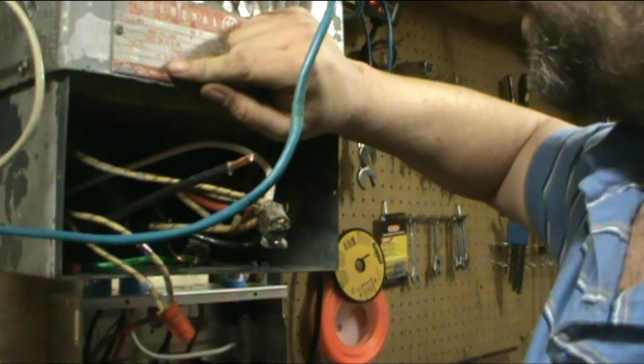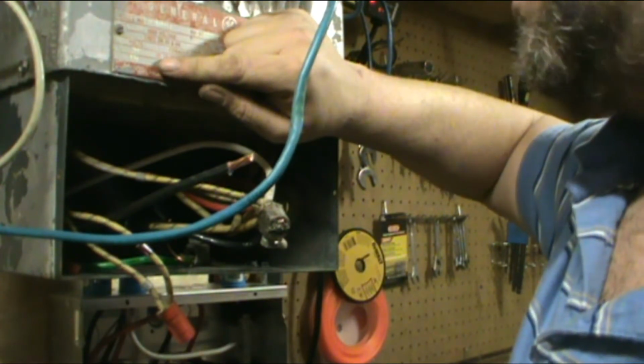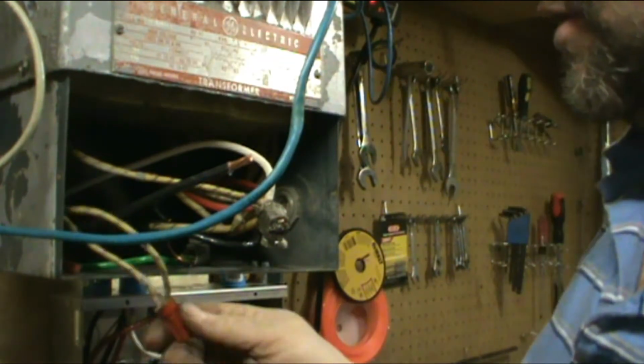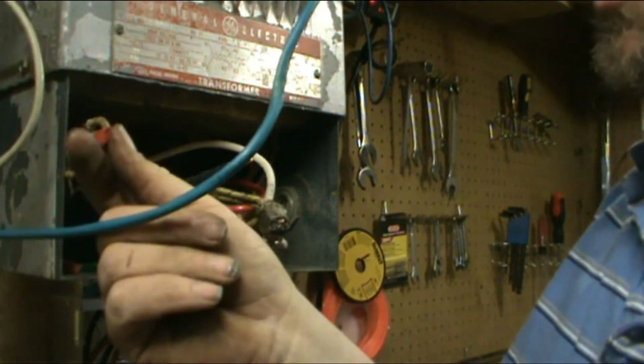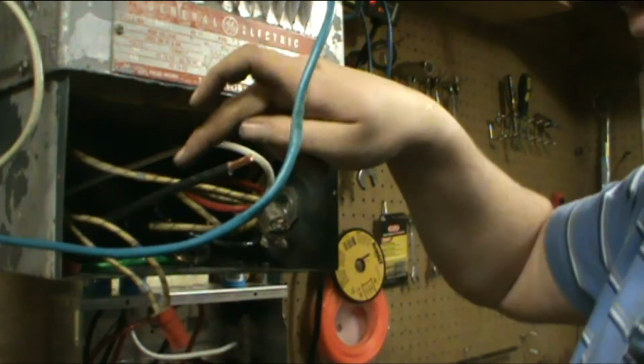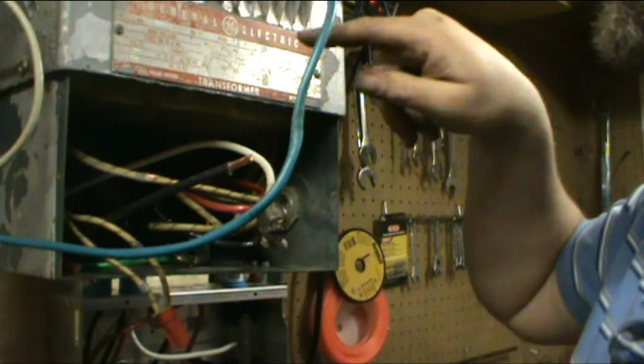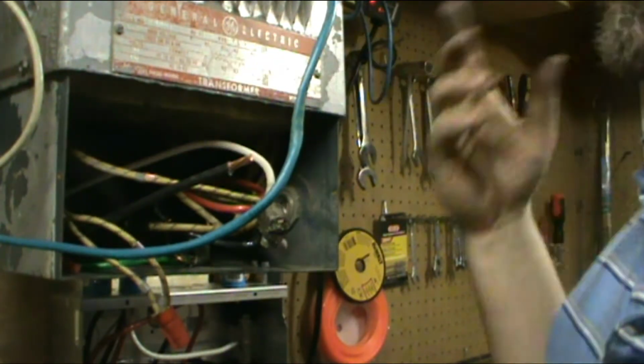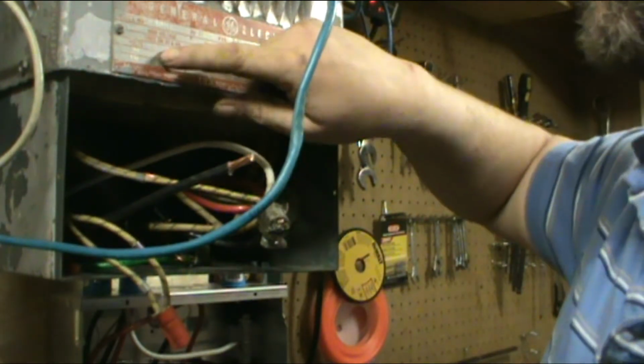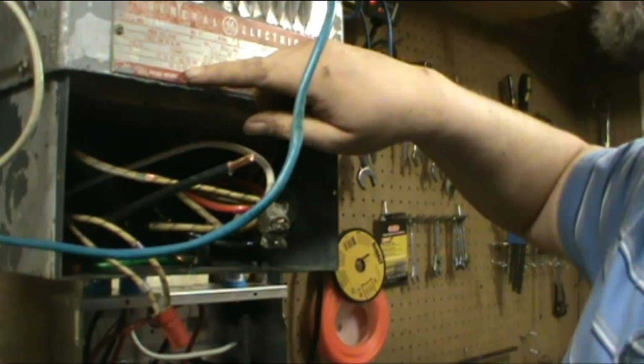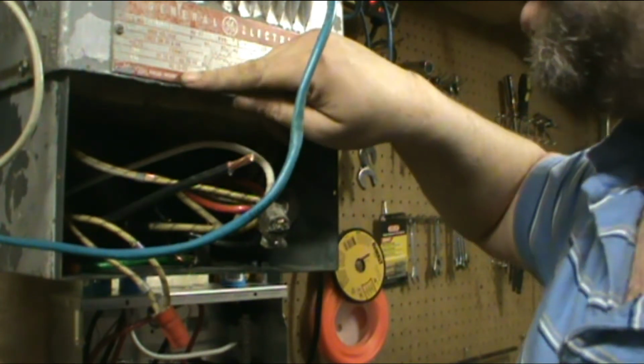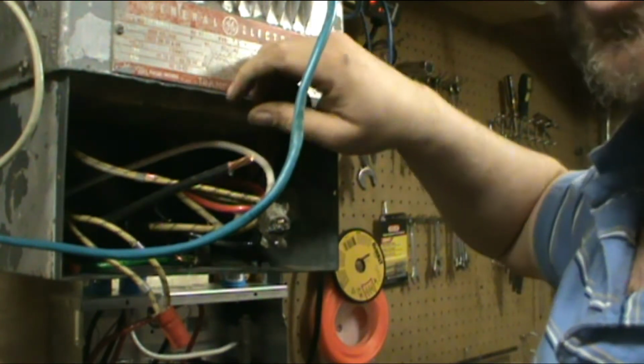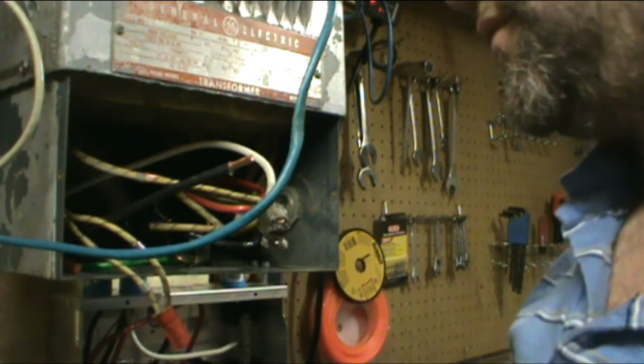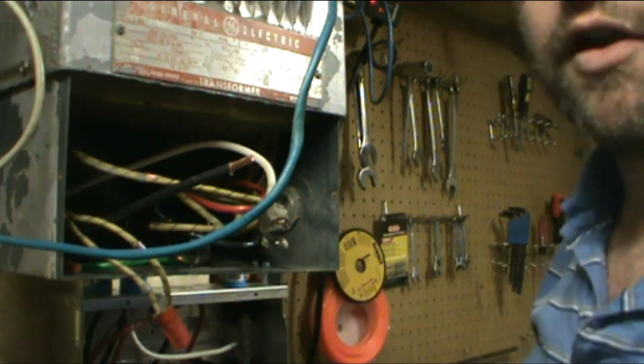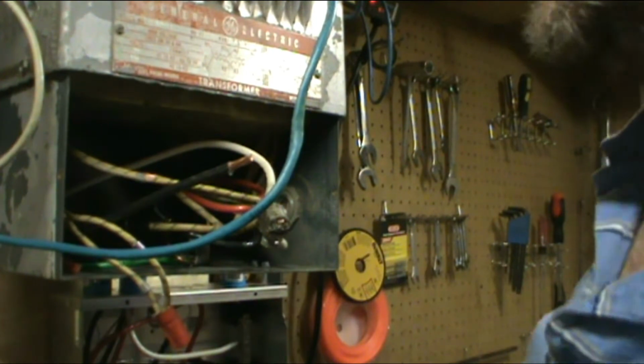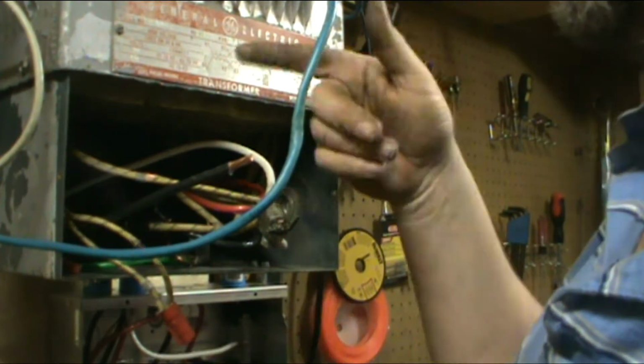But we got 240. And to set 240 up, I'd wire H1, H3, which is those two wires in parallel. And the same way with these two lines that are going in this neutral lug, they're in parallel. So one side's my neutral, one side would be my hot. If I wanted 480, I'd wire H2 to H3, put a ferrule on those, and then your two other leads would give you 480 volts. So that's running it in series. But I'm running the lines in parallel to keep me at 240.